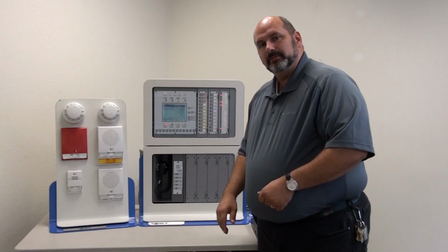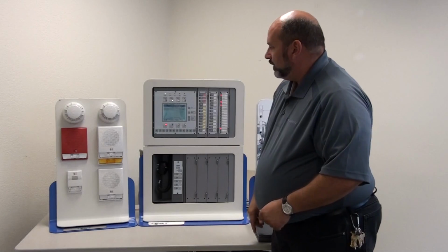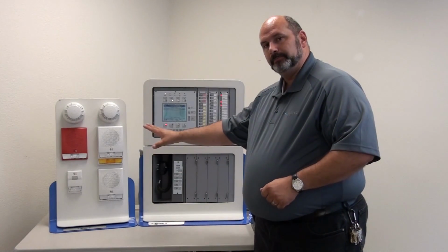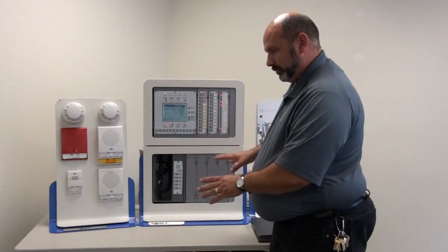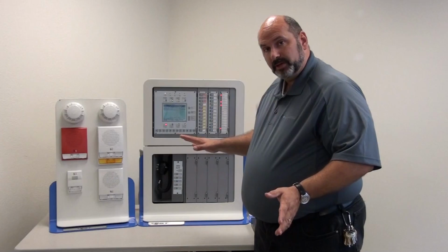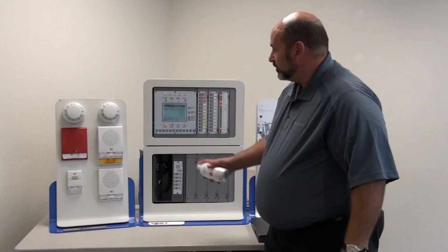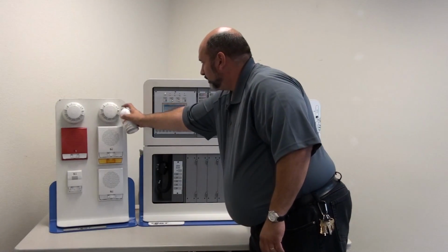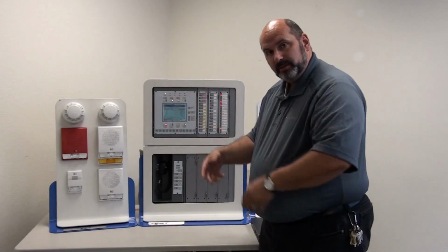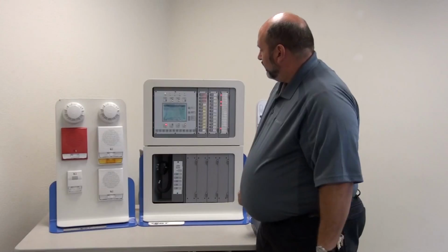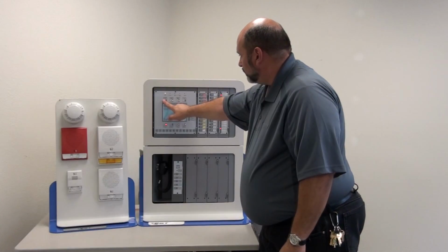But let's say somebody burned the popcorn, so we're going to go ahead and alarm silence, and that will stop the audibles from ringing. Now, you may still have strobes, but the alarm will remain silent. That's just a warning for everybody. Once you know where the cause of the alarm is and you've resolved the cause, or you've cleaned out the smoke detector, or you've reset the pull station that somebody knocked off the wall or whatever, once you've resolved your alarm condition, then you can reset.